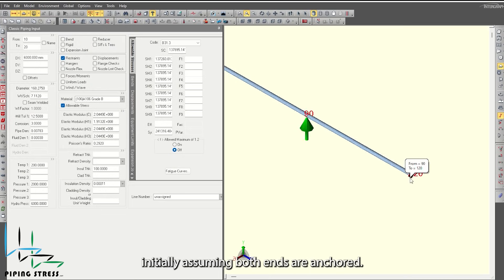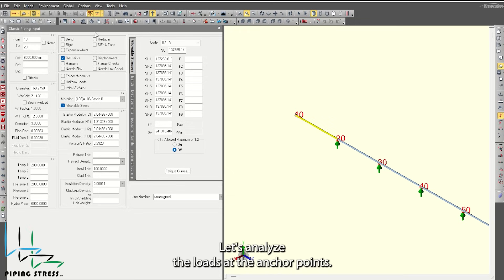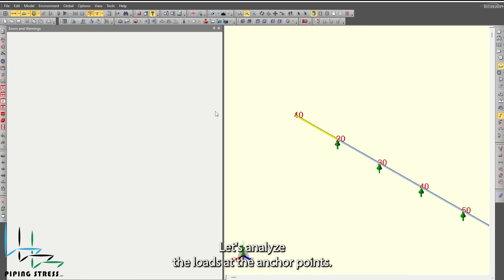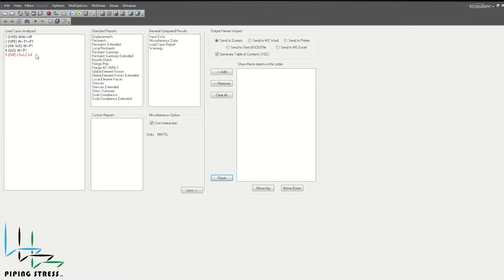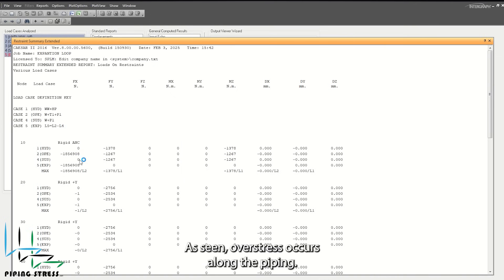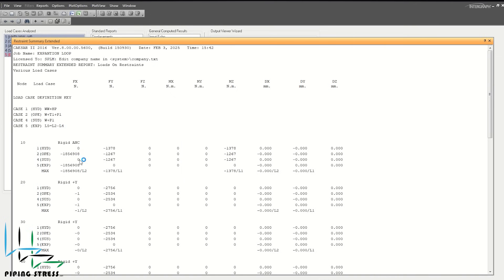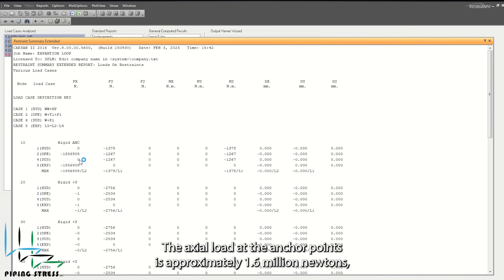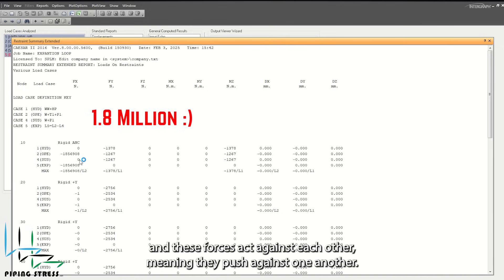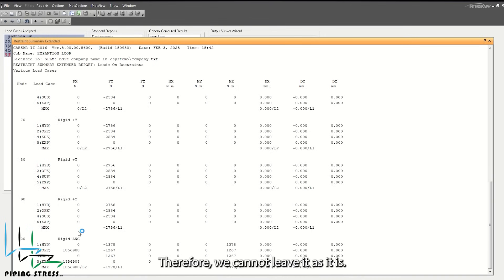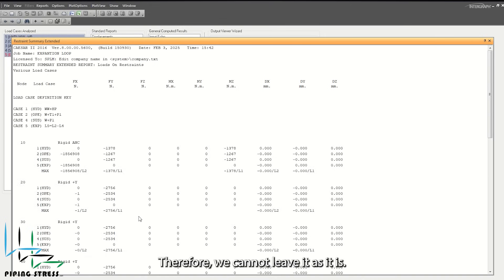Initially, assuming both ends are anchored, let's analyze the loads at the anchor points. As seen, overstress occurs along the piping. The axial load at the anchor points is approximately 1.8 million newtons, and these forces act against each other, meaning they push against one another. Therefore, we cannot leave it as it is. Anchors are not very realistic for straight pipelines.